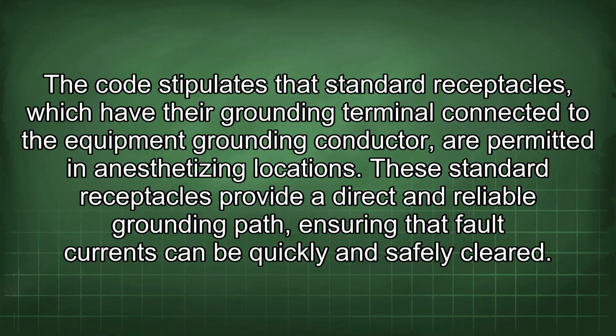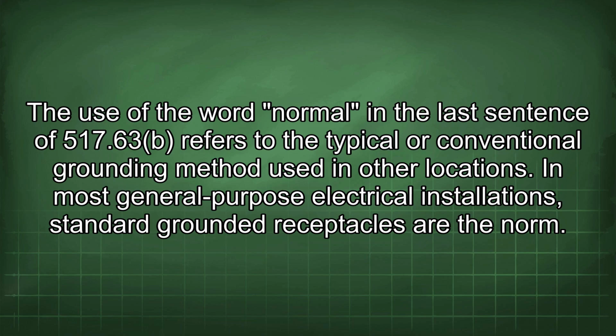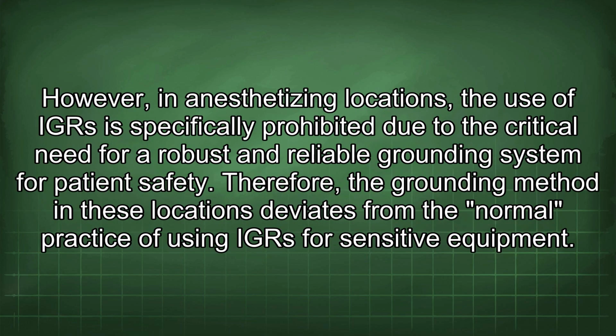The use of the word normal in the last sentence of 517.63 refers to the typical or conventional grounding method used in other locations. In most general-purpose electrical installations, standard grounded receptacles are the norm. However, in anesthetizing locations, the use of IGR is specifically prohibited due to the critical need for a robust and reliable grounding system for patient safety. Therefore, the grounding method in these locations deviates from the normal practice of using IGR for sensitive equipment.